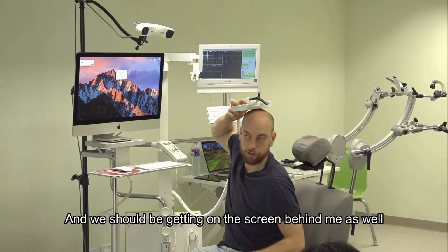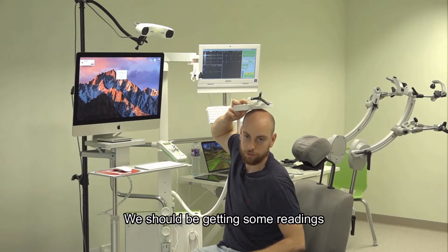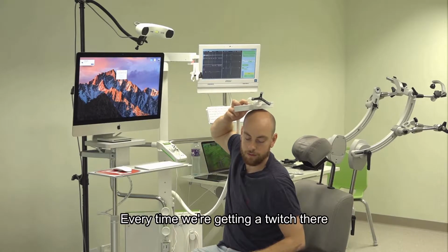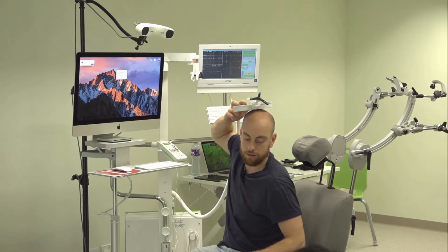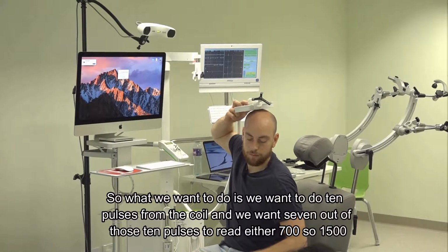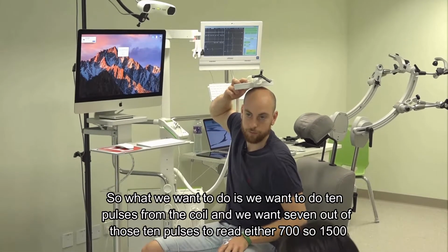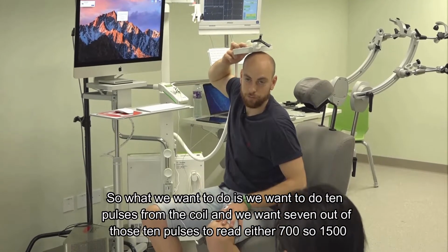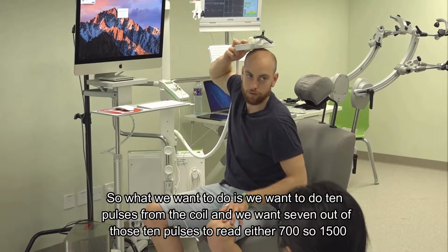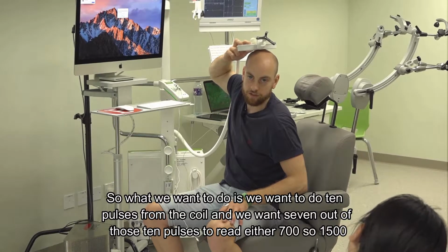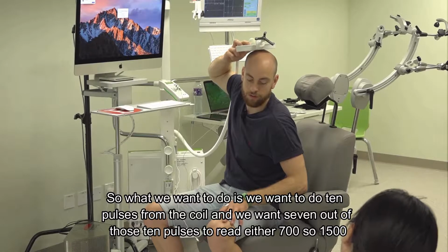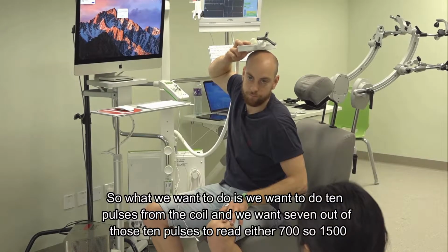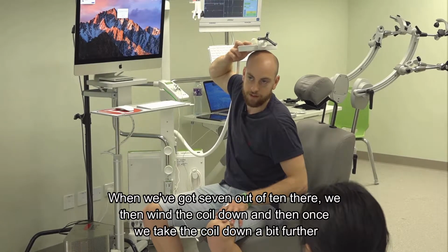And we should be getting on the screen behind me as well, we should be getting some readings every time we're getting a twitch there. So what we want to do is we want to do 10 pulses from the coil, and we want 7 out of those 10 pulses to read either 700 to 1500.